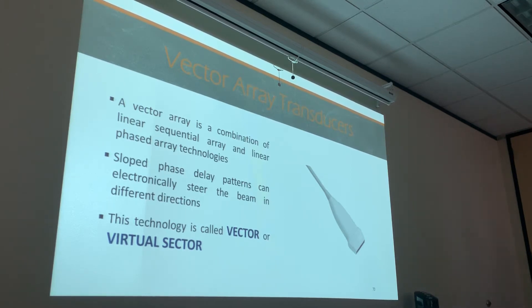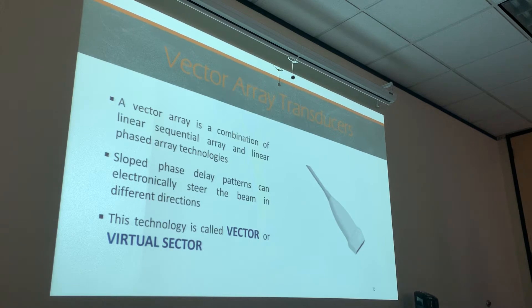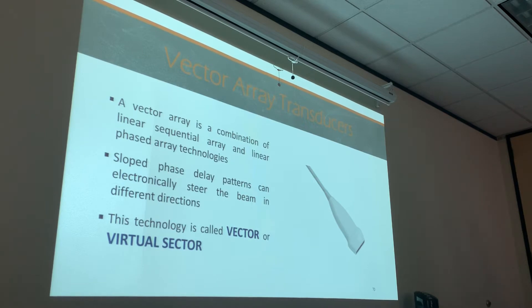So, Vector Array Transducer is a combination of the Linear Sequential Array Transducer and the Linear Phase Array Transducer. That's what I want you all to remember about the Vector Array — it's a combination of both. Sloped phase delay patterns can electronically steer the beam. Remember our two S's: slope equals steer.